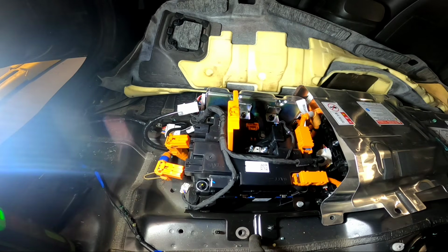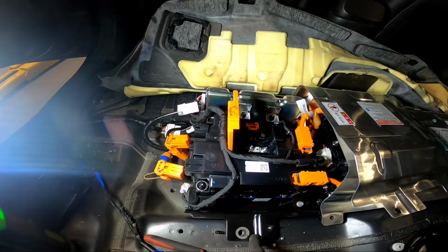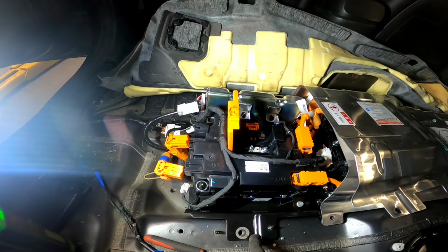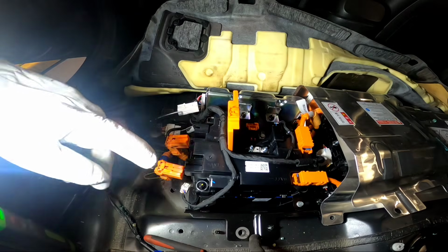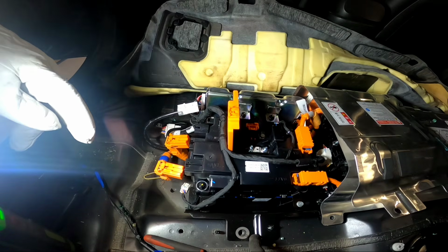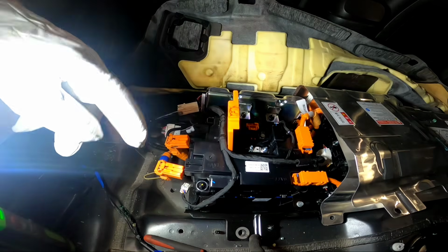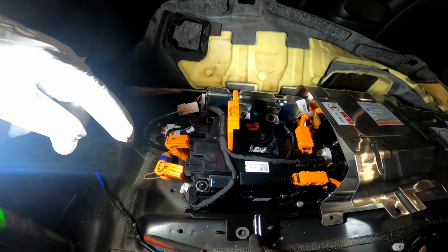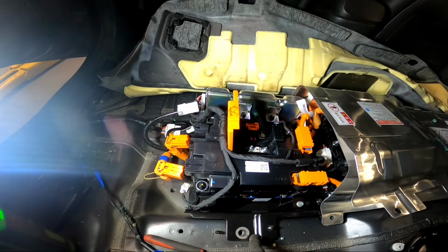Unless what happened here is the coil itself is stuck, or the switch on the relay stuck closed. So the coil is okay, but the switch itself is closed. I think that's what's going on here. But we heard on our actuation last time that it's clicking on the minus side, but not on the plus side. That's why we called the relay, because we thought that our wiring diagram is correct. Pin 2 and 3, that's the main plus, but actually it's pin 2 and 4. Pin 2 and 3 is the pre-charge.